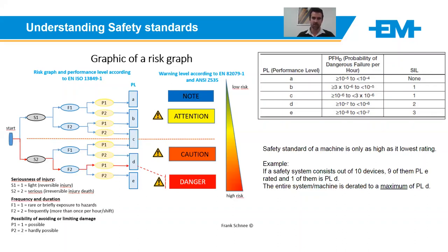So also important to note that a safety system is really only as strong as its weakest link. So if your whole system is made up of PLE devices, from controllers and actuators, but you've got one sensor that's a PLD, then the whole system conforms to a PLD standard. Also something to consider when designing.